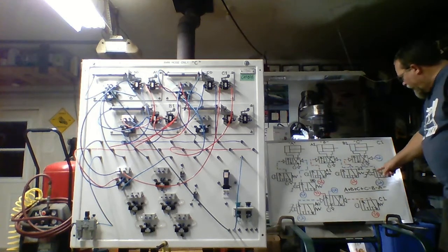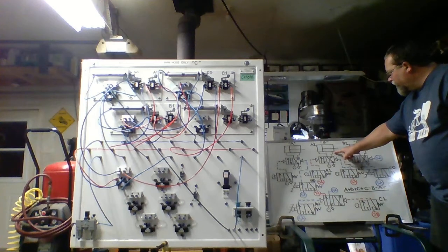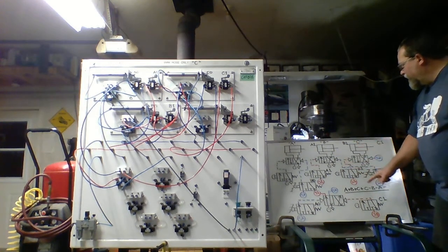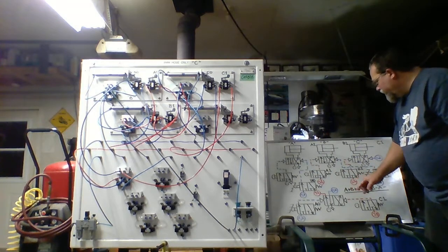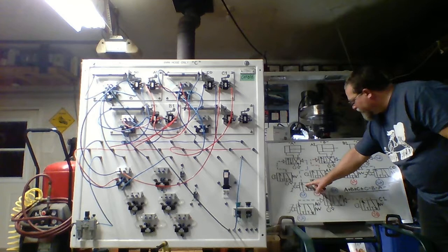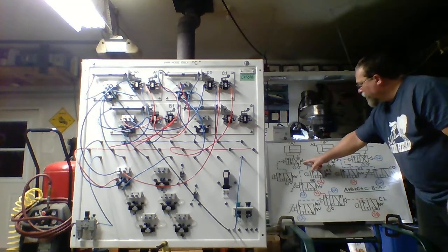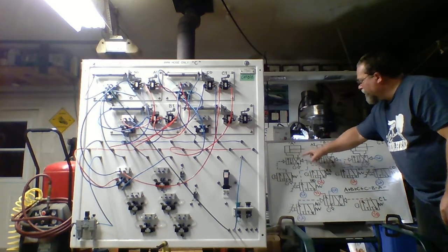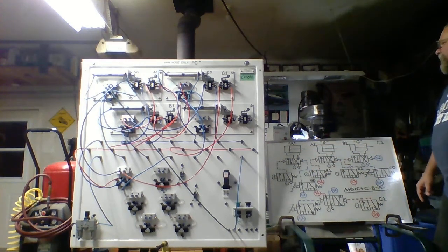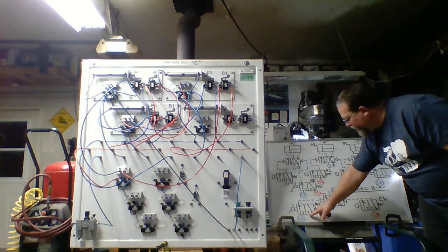We look at the flow path, and it's going to pilot the 4 two-way for B, charging the rod end, having B retract. And when that happens, that gets on B0. We look at B0 over here. It's supplied by source 2. Again, the same as C0. It's held open. It's going to pilot the 4 two-way for A and have that shift, and of course charge the rod end for cylinder A. When A retracts, it gets on A0.